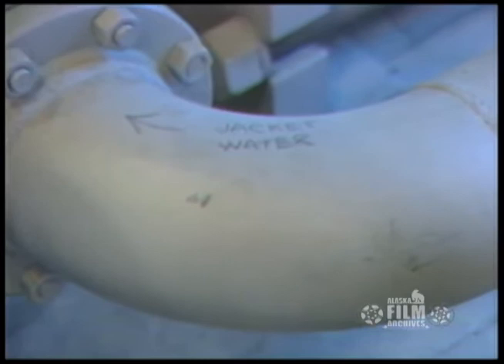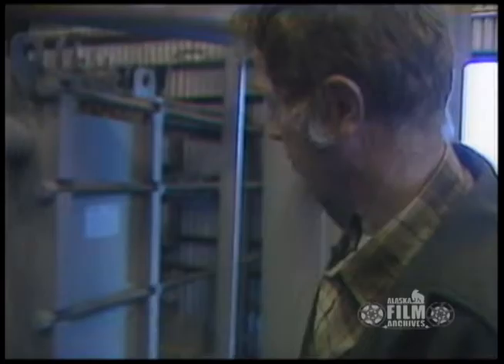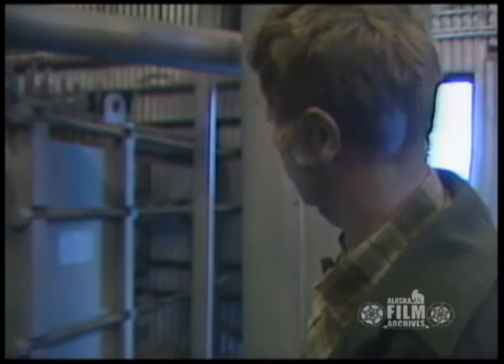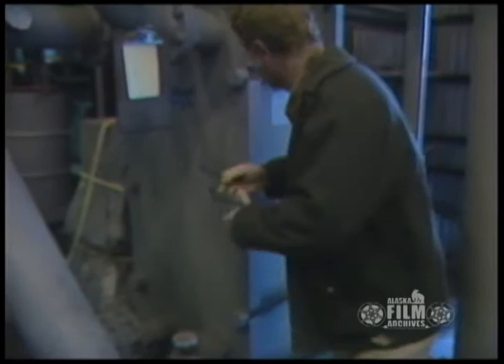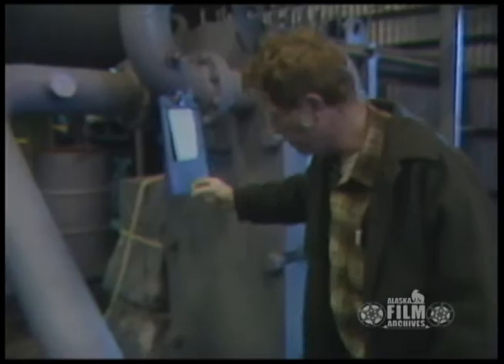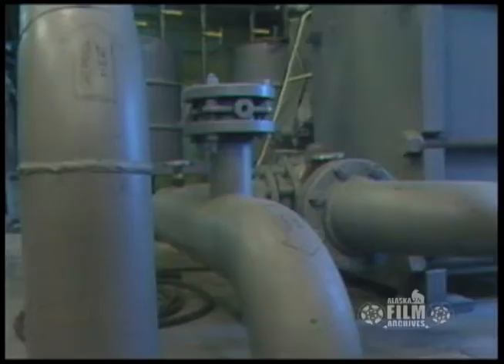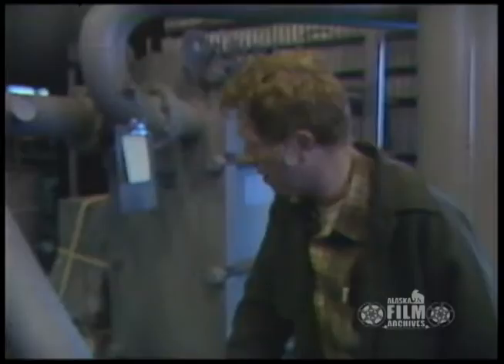This is a jacket water cooling system for all of the engines in the powerhouse. The jacket water goes into the heat exchanger, warms it up, and goes back out here. At the same time, it heats up a pipe which goes all the way up to the grade school and its heat exchanger, and then the return comes back here.